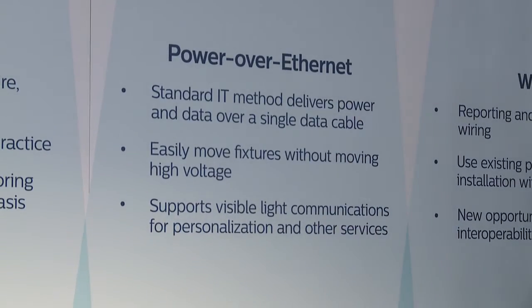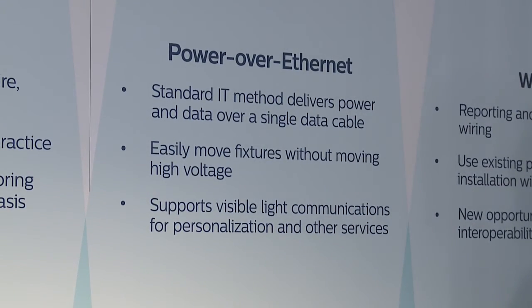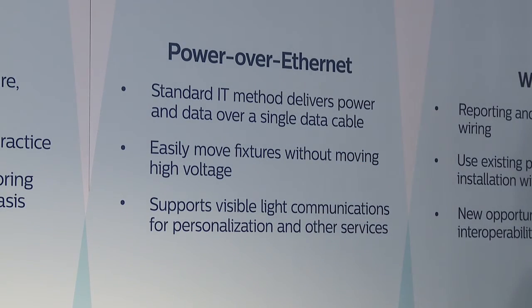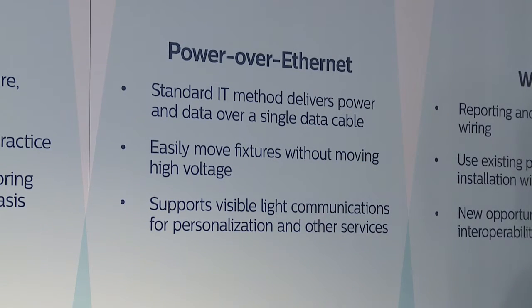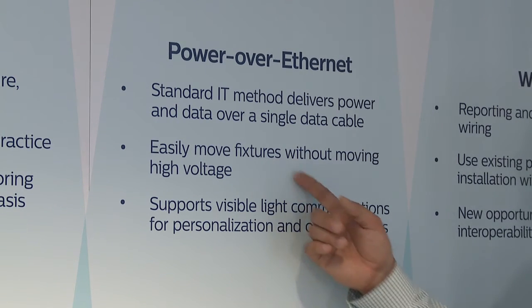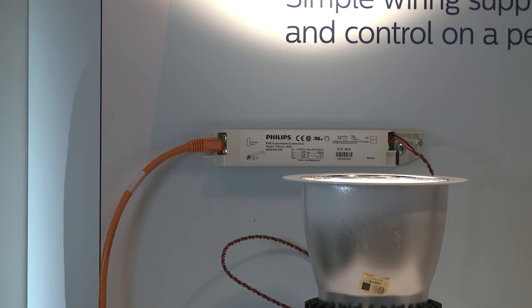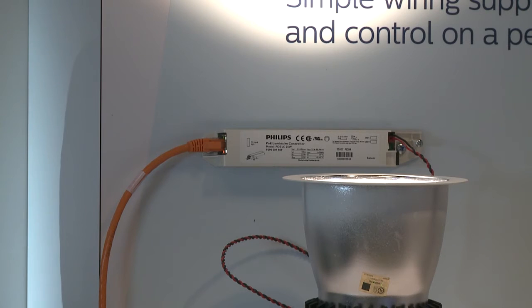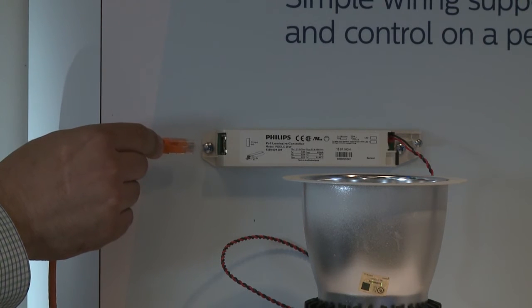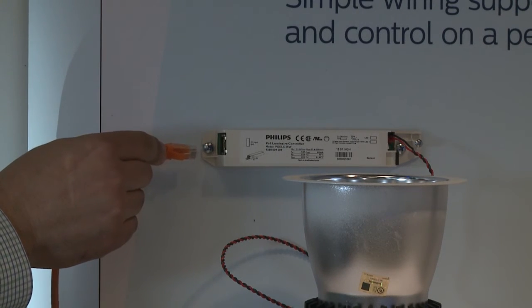Power over Ethernet is the newest way to connect luminaires to a lighting system. It uses standard IT methods to deliver power and data over a single CAT 6 or CAT 7 cable. You can easily move fixtures around without having to deal with high voltage, and it supports visible light communications for personalization, personal control, and other services coming in the future. Power over Ethernet lights — we're showing a Calculite fixture right here — allow power and data to be sent to the fixture through a standard CAT 6 or CAT 7 line. In this case, when I remove the Ethernet cord, we lose the light and the data to the fixture.